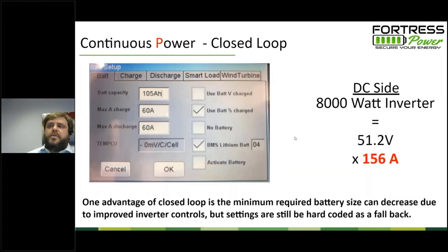Even with closed loop, a lot of installers say, I really want closed loop because that means I don't have to program the inverter anymore. You still want to go through the process of programming the inverter, even though technically the battery management system is overriding those communication protocols, in case the battery management system were ever to lose connection with the inverter, which could easily happen with an inverter manufacturer firmware upgrade. So even if you're doing a closed loop communication system, you still want to program the open loop settings.